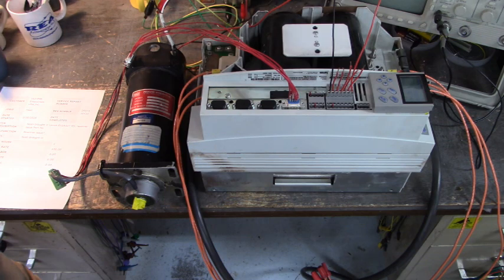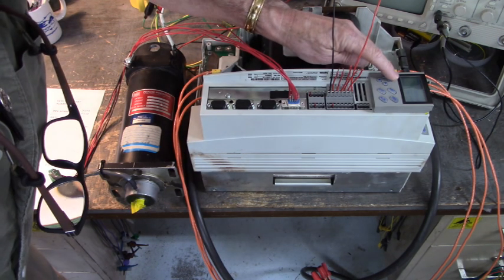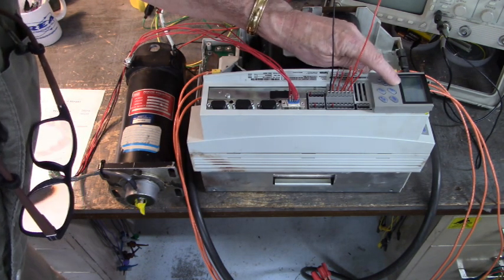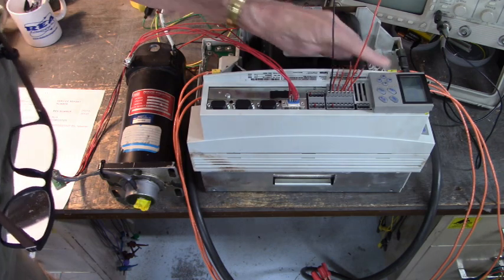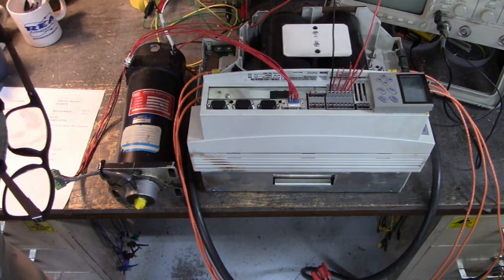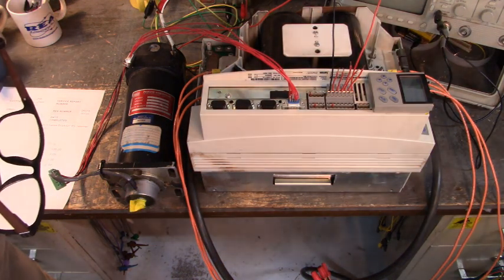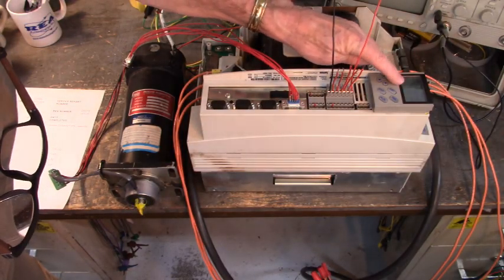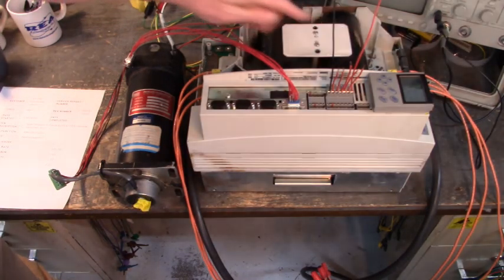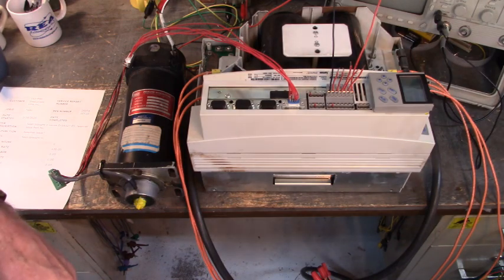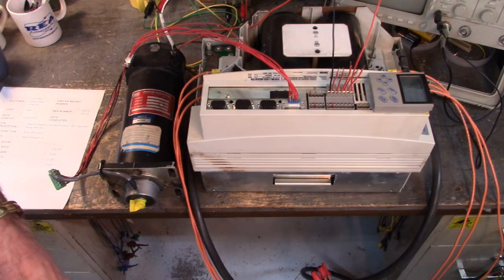I'm going to turn it on again. With the drive stopped, in the display, it says STP1. Stop 1. There. Now, stop 1 has disappeared from the display. And the light bulbs are sequencing through U, V, and W.